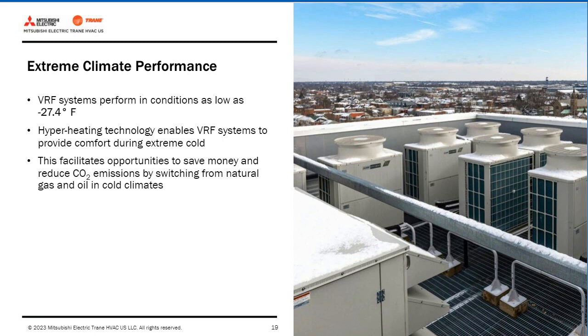Contrary to the outdated ideas based upon long discontinued equipment, today's VRF heat pumps are able to provide heating in extreme cold. VRF systems can perform in conditions as low as negative 27.4. With my 10 years of experience in the engineering field before this, that seems not realistic, but we have a lot of systems installed in areas that have hit this temperature, and it functions in the negative 27 degree temperatures.